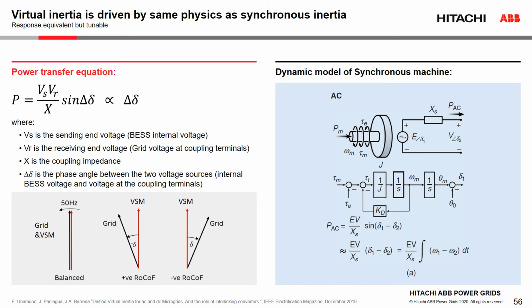This is how you get an inherent real power response from a virtual synchronous machine without the need to measure. It is not looking at what the grid frequency is doing and responding. The grid moves away from the virtual synchronous machine and the power contribution is a consequence. Now, how the virtual inertia coefficient is set will not dictate the initial response, but it will define how fast or slow the red phasor catches up with the grid.